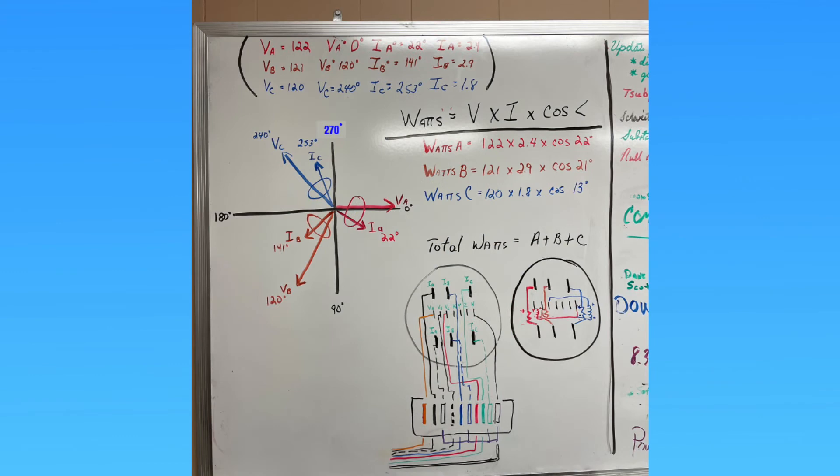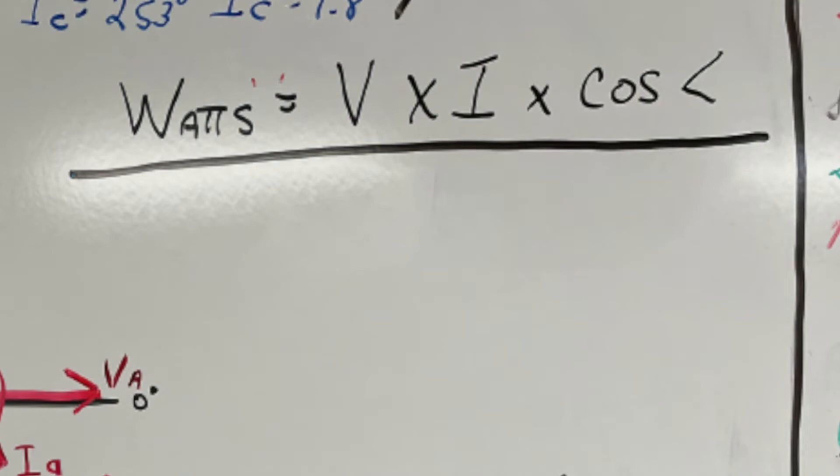Here are some given values at a site that we wrote down on the PowerMaster. Now we're going to go to the watts calculation and the formula for watts is volts times amps times cosine of the angle.